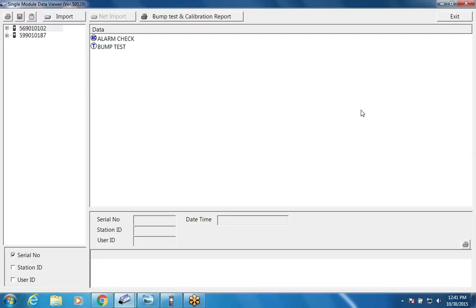This unit is an expansion module. You can connect up to 3 calibration gases on one dock, but there are some versions of sensor combinations where you might need more than 3. So this is basically a solenoid valve expander that allows you to connect 6 gas bottles at once. I don't know how many combinations there are that require that—there's not very many, but there are some. This was designed so that with any sensor combination, you can have enough gas bottles to calibrate all the sensors at once. Show how it connects on the end there.